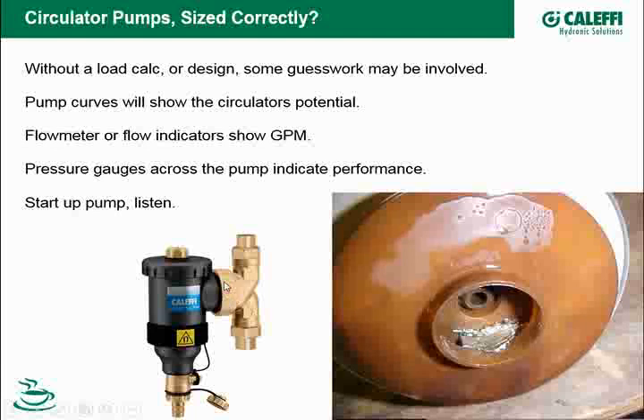This is nice that you can turn this. You loosen this nut here, and you can turn this and use it as a vertical or a horizontal application, and it's also got the magnetic band on it. So that's one of many different versions that are out there, but it's going to just protect all the components in the system, not only the pump, but zone valves, balancing valves, heat exchangers.